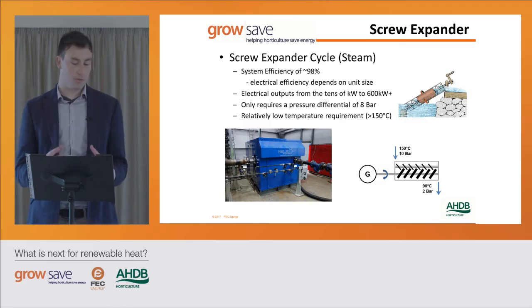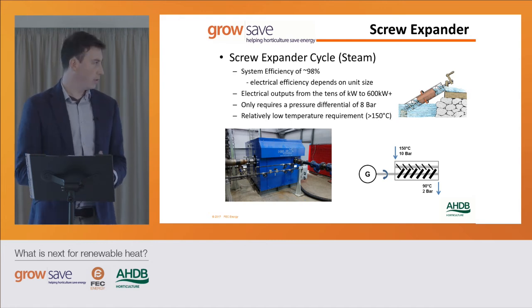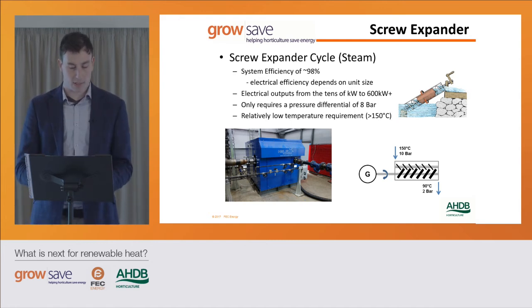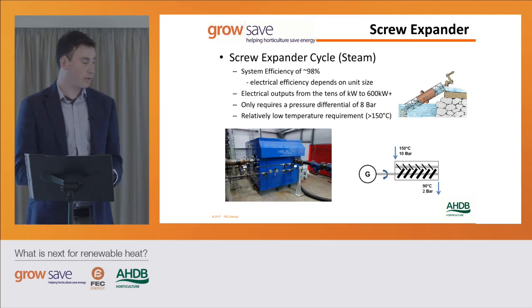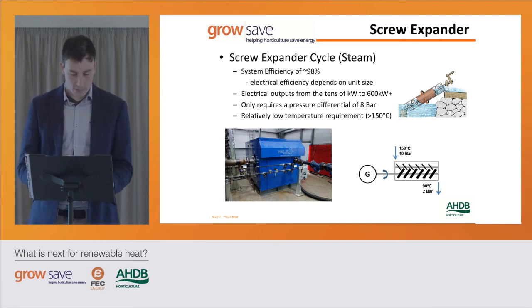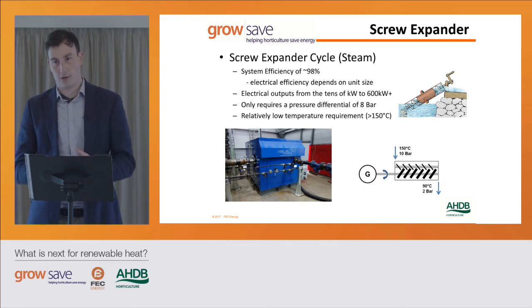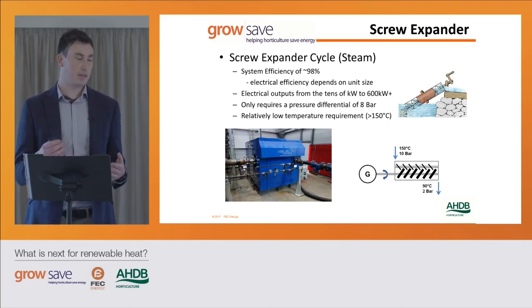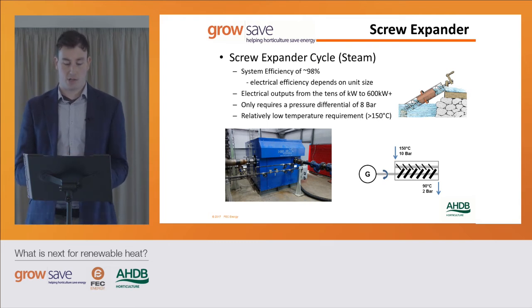The system uses two rotors which turn at relatively slow speeds compared to a steam turbine, and you can power it with wet steam as opposed to a turbine—so it can be a mix of steam and water to generate. You can't use that in a turbine because of corrosion effects. Also, while a turbine has very fixed operating conditions—fixed pressure and temperature—a screw expander can operate at a variety of different pressures and temperatures.